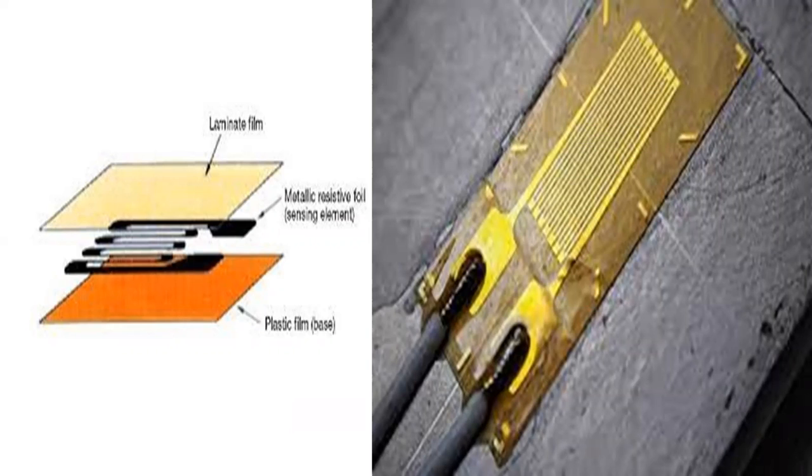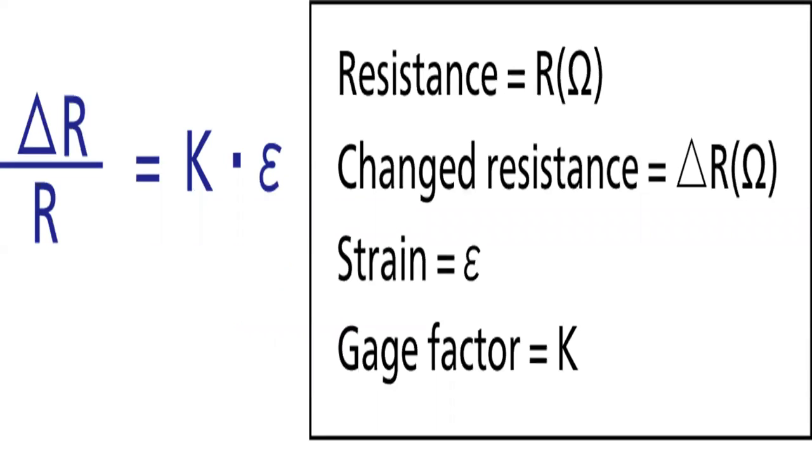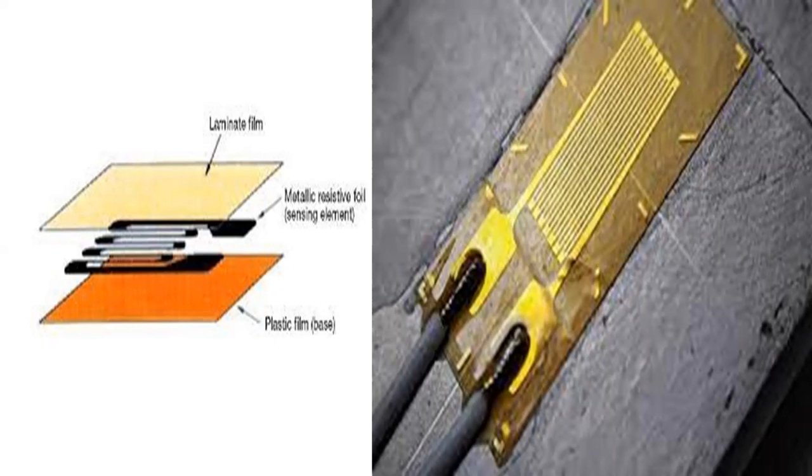Strain gauge-based technology is used commonly in the manufacture of pressure sensors. The gauges used in pressure sensors themselves are commonly made from silicon, polysilicon, metal film, thick film, and bonded foil. Each strain gauge is composed of metal foil insulated with a flexible substrate, as shown in the figure. The two leads pass a current through the gauge, and as the surface of the object being measured stretches or contracts, the change in resistance is measured. This change in resistance is proportional to the change in length on the surface of the object being tested, as shown in this equation.